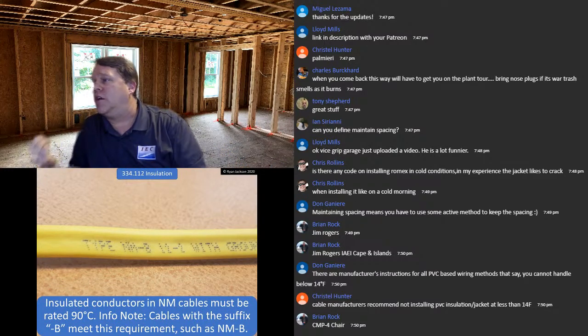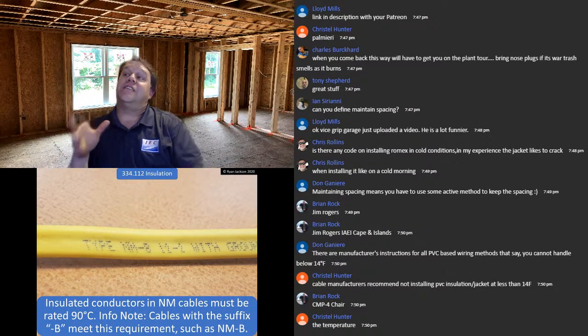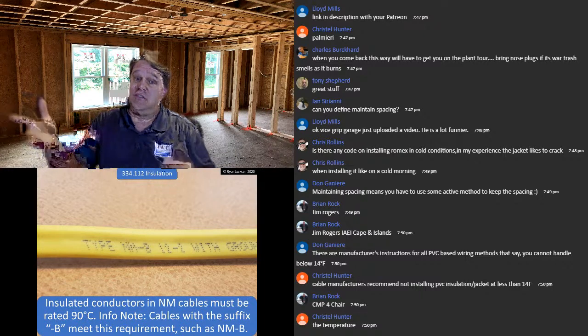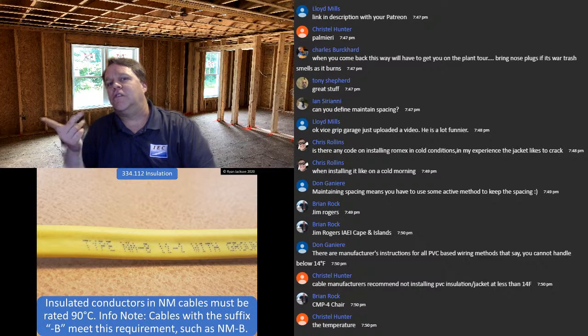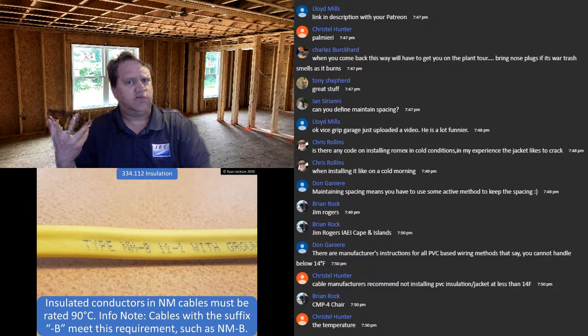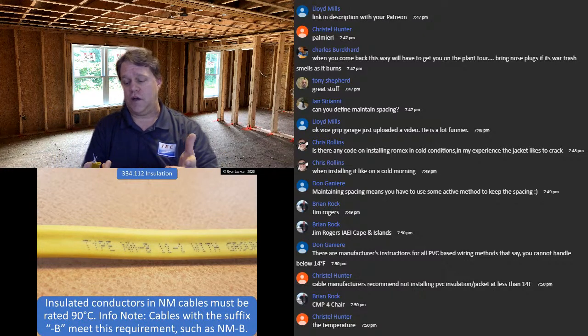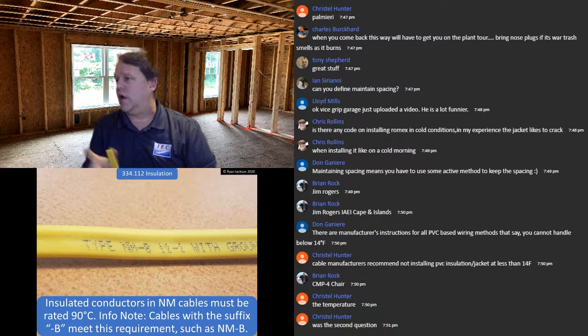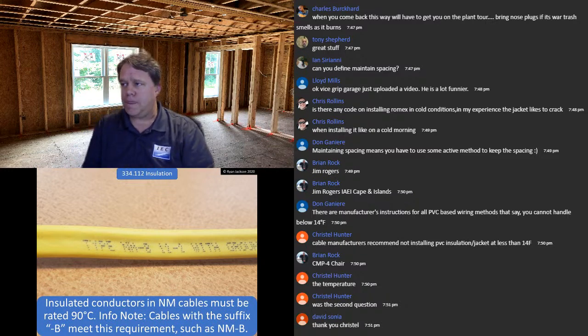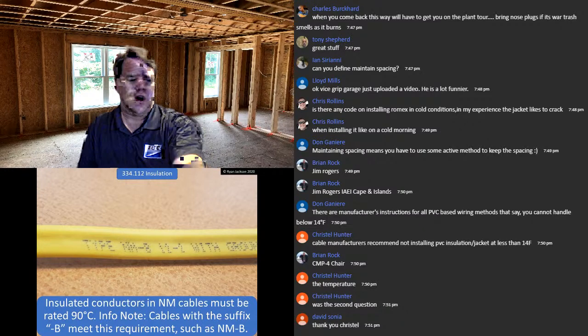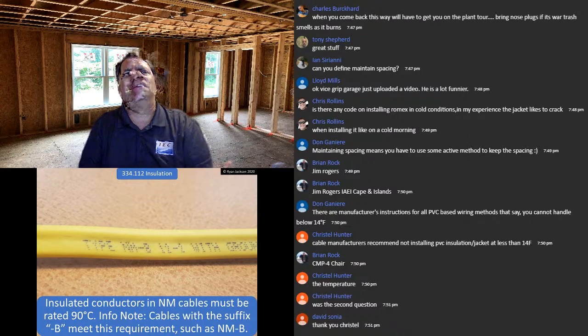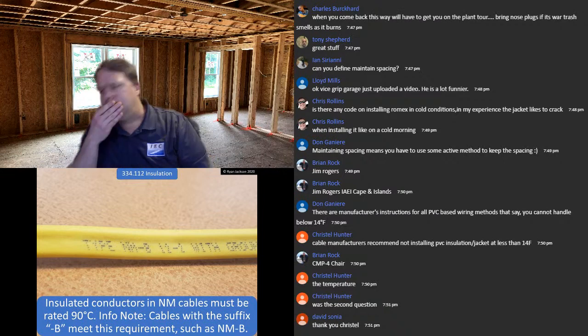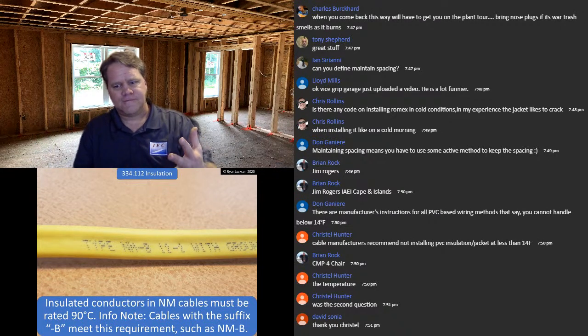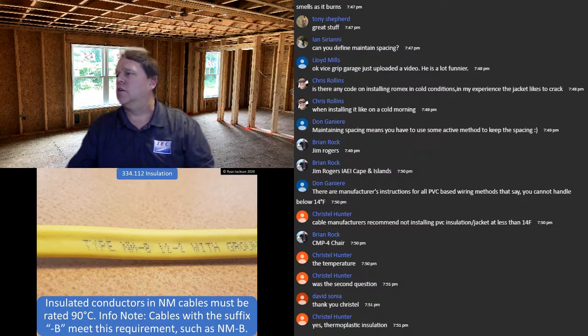Okay, so cable manufacturers recommend not installing PVC insulation jacket at less than 14°F. And by the way, when Crystal says that, she's a cable manufacturer. She knows what she's talking about. And Chris, that is true for thermoplastic insulation, right? Not just the cable sheath, but THWN. Okay, perfect. So, yeah, not colder than 14. And then XHHW, cross-linked polyethylene, is okay colder than 14 degrees F, I think. Whatever I just said, thermoplastic is not. What is the thing you can't use colder than 14°F? It's not thermoplastic. It's, I don't know, the polymer or whatever it is. Oh, it is thermoplastic. Okay, cool. All right, got one right.